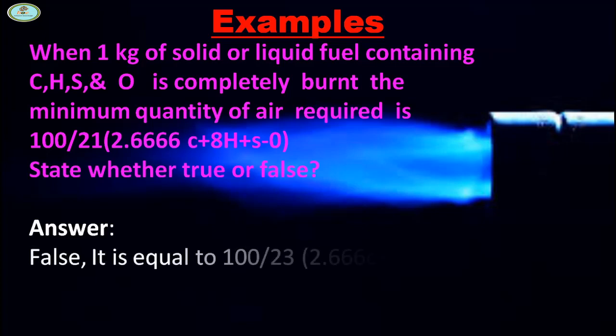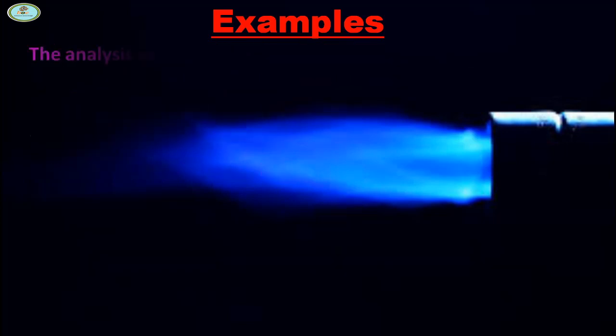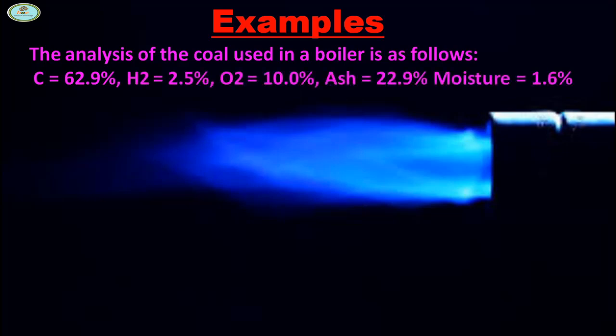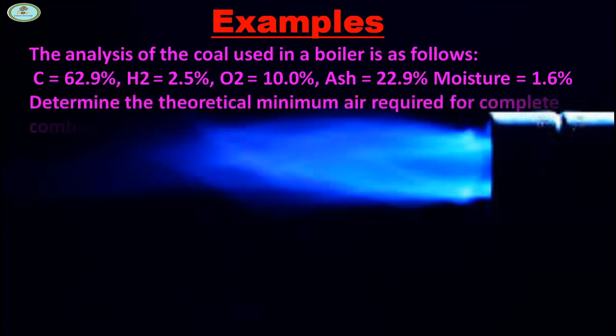It is equal to 100/23 × (2.666C + 8H + S - O). The analysis of the coal used in a boiler is as follows: C = 62.9%, H2 = 2.5%, O2 = 10%, Ash = 22.9%, moisture = 1.6%. Determine the theoretical minimum air required for complete combustion of 1 kg of coal.